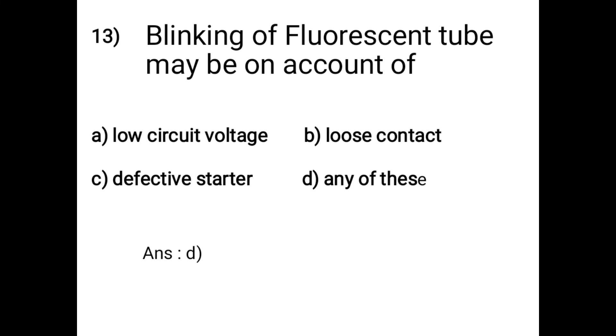Question 13: Blinking of a fluorescent tube may be on account of: A - low circuit voltage, B - loose contact, C - defective starter, D - any of these. The answer is option D: any of these. Blinking of a fluorescent tube may be on account of low circuit voltage, loose contact, and defective starter.